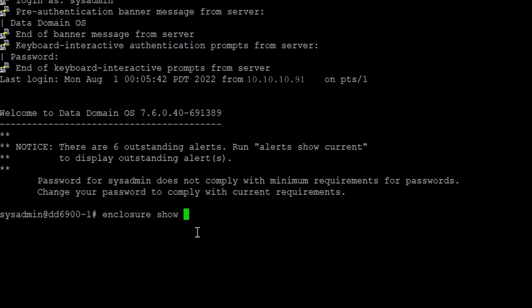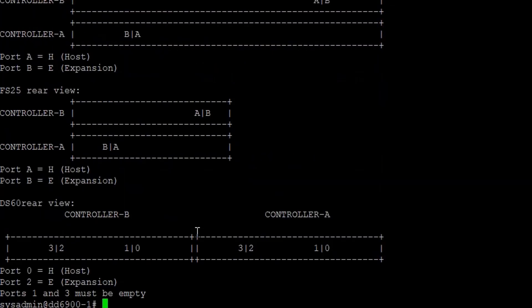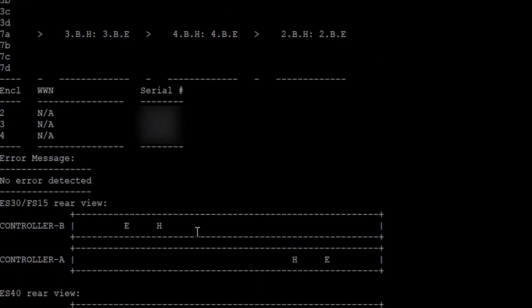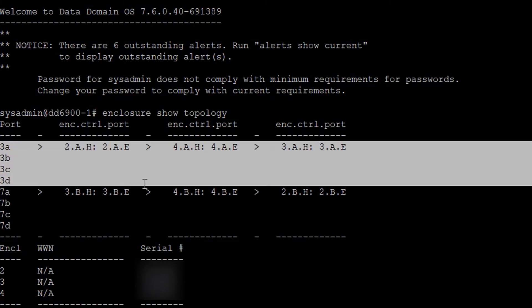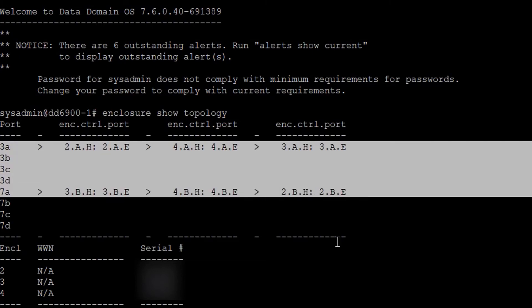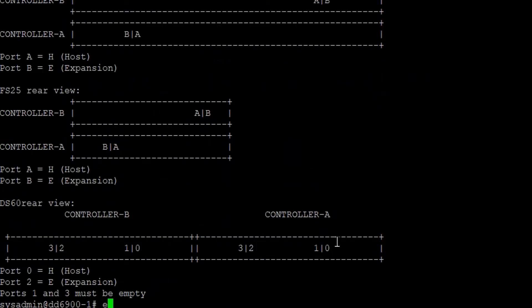Step 8: Check whether the enclosure topology is correct. Check whether any error appears with an asterisk next to the ENC control dot port field. Test communications on the ports with cables connected for 5 minutes. If there is an error, it is recommended to reseat the cables or LCCs.